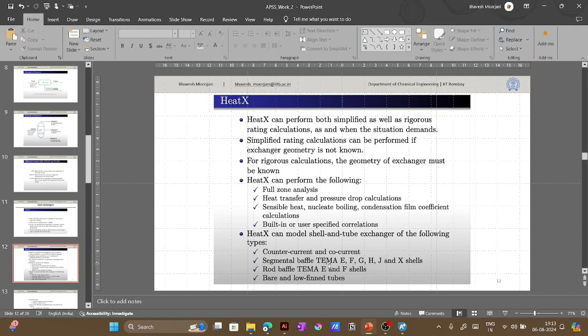Based on that TEMA standard, notations like E, F, G, H, J are used for segmentation level, flow arrangement, whether it's one pass or two pass or three pass on the shell side, how many passes on the tube side, and so on. If you don't know it, I recommend searching it on Google. You'll find various TEMA standards used in industry, particularly for those working in the design field. You must know these standards, as they help determine the specification of the heat exchanger, specifically the geometry part.